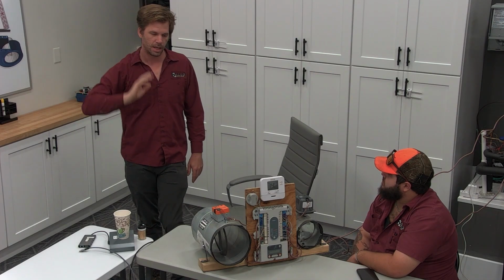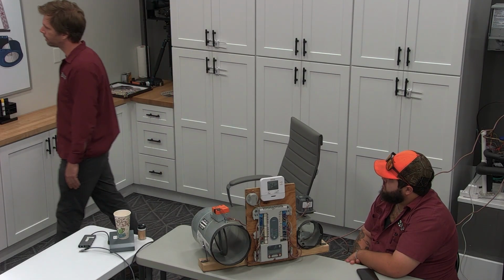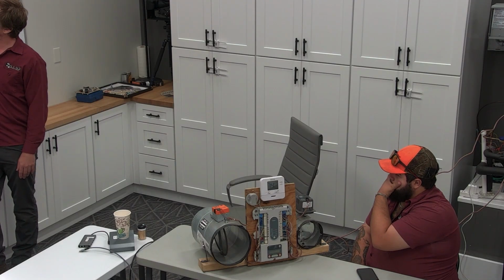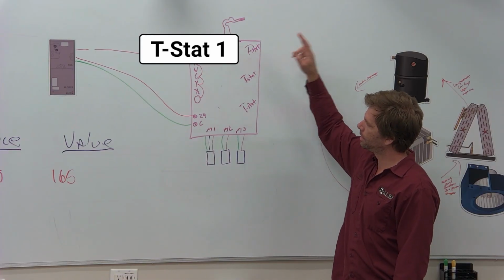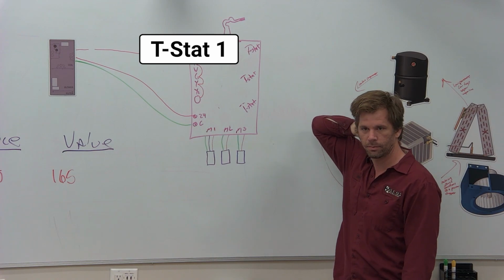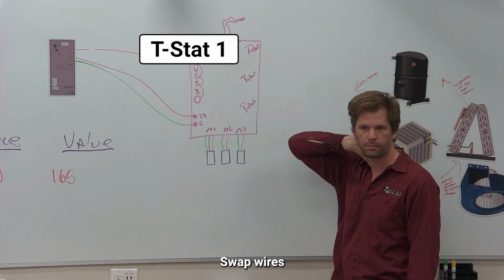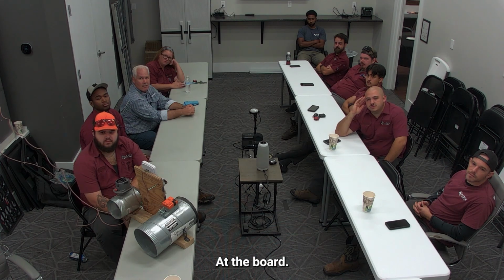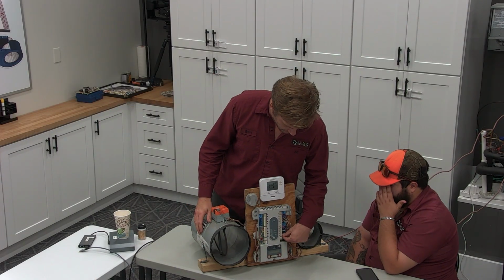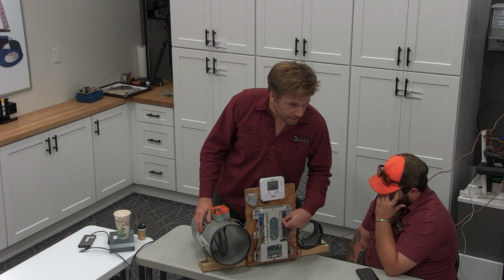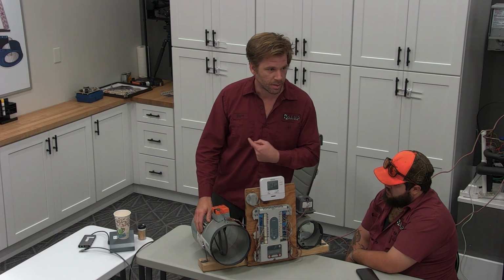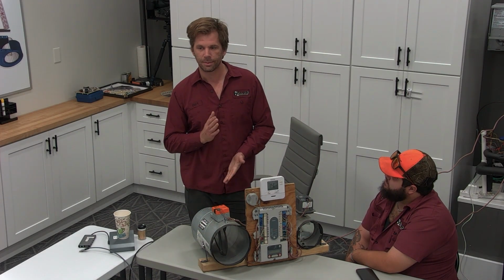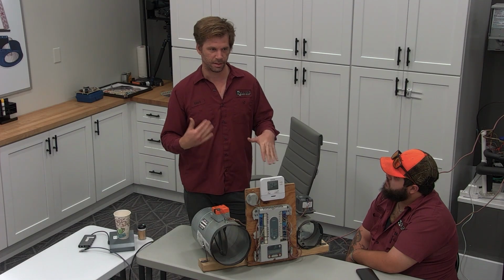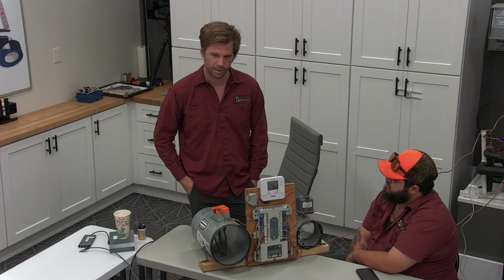And so if you have a scenario where T-stat 1 is not actually controlling zone 1, how do we fix that problem? Swap wires. Swap wires where? At the board. We don't crawl up in the attic and start moving wires from one motor to the other, right? We just go right here and unplug that wire, plug it in with the other thermostat, swap it around, go straight back and confirm. And now we know we need to do that with every single zone in the house. There's likely some mix-ups going on there, right?